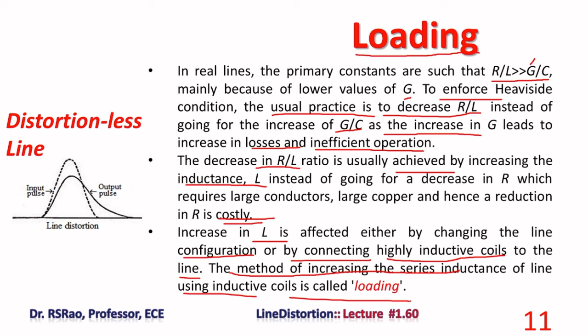Increase in L is effected either by changing the line configuration or by connecting highly inductive coils to the line. The method of increasing series inductance of the line using inductive coils is called loading. Changing the configuration of the line, once it is established and in place, is quite a difficult task. What we do is go for loading. Inductance coils are used for loading. They are traditionally known as Pupin coils, and the process of inserting them is called Pupinization.